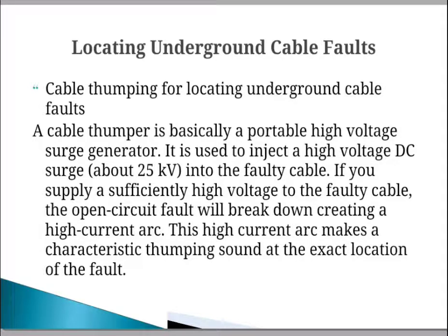A cable thumper is basically a portable high voltage surge generator. It is used to inject high voltage DC surges into the faulty cable. If you supply sufficient high voltage to the faulty cable, the open circuit fault will break down, creating a high current arc. This high current arc makes a characteristic thumping sound at the exact location of the fault.